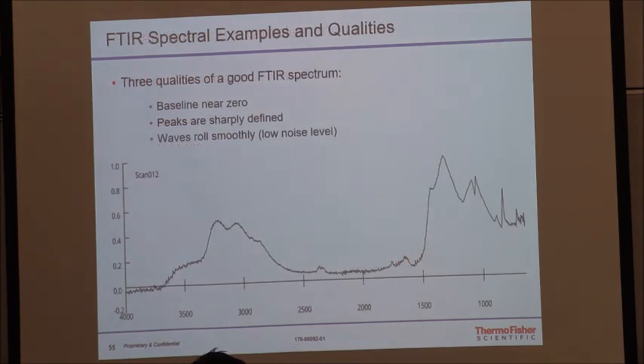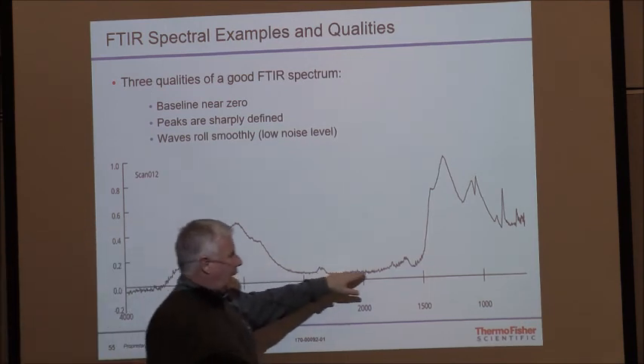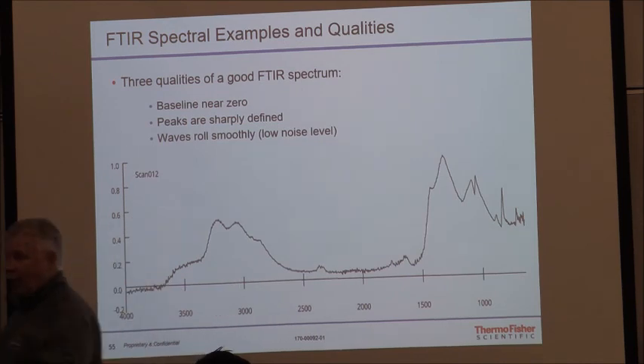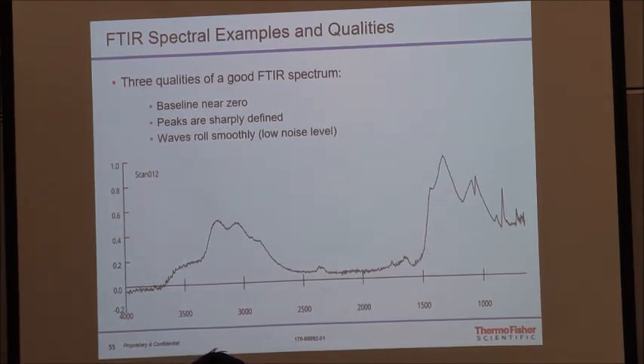What about that spectrum right there? Notice the zero dropped a little bit, it's kind of fuzzy, but it comes up, it kind of flattens. So if I got a no match and I saw that spectrum, did it tell me that I really did anything wrong? No. It's just saying there's something weird going on here. Either reposition it, rerun it. That one is an FT spectrum. If you ran it on that, I'd re-clean it, and maybe try it on the Raman or something that way as well. Okay?